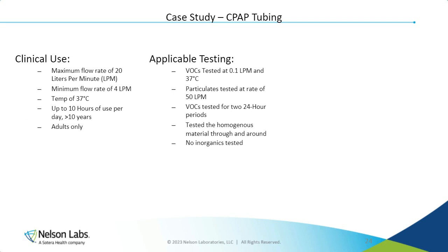Let's look at a real quick case study for, let's just say, a CPAP tube. Consider, for example, a tube that carries air to the patient at a maximum flow rate of 20 liters per minute. This has a minimum flow rate of 4 liters per minute, and the air is no hotter than 37 C. This device will be used in adults only for a maximum of 10 hours per day for greater than or equal to 10 years. The device was then tested for VOCs at 0.1 liters per minute at 37 C over two 24-hour periods. Then particulates were tested at 50 liters per minute. There were no inorganics tested.